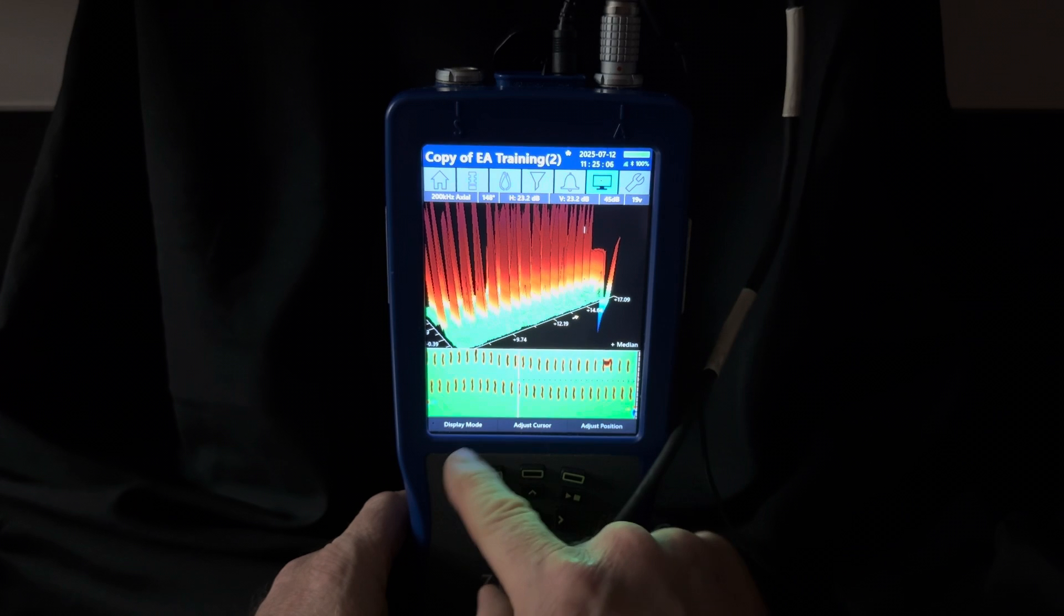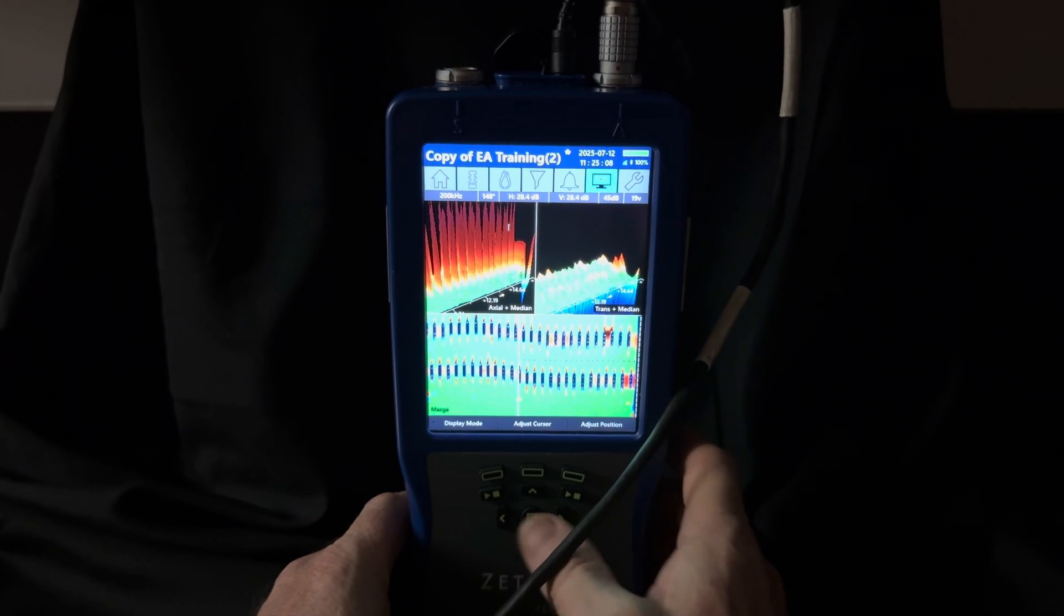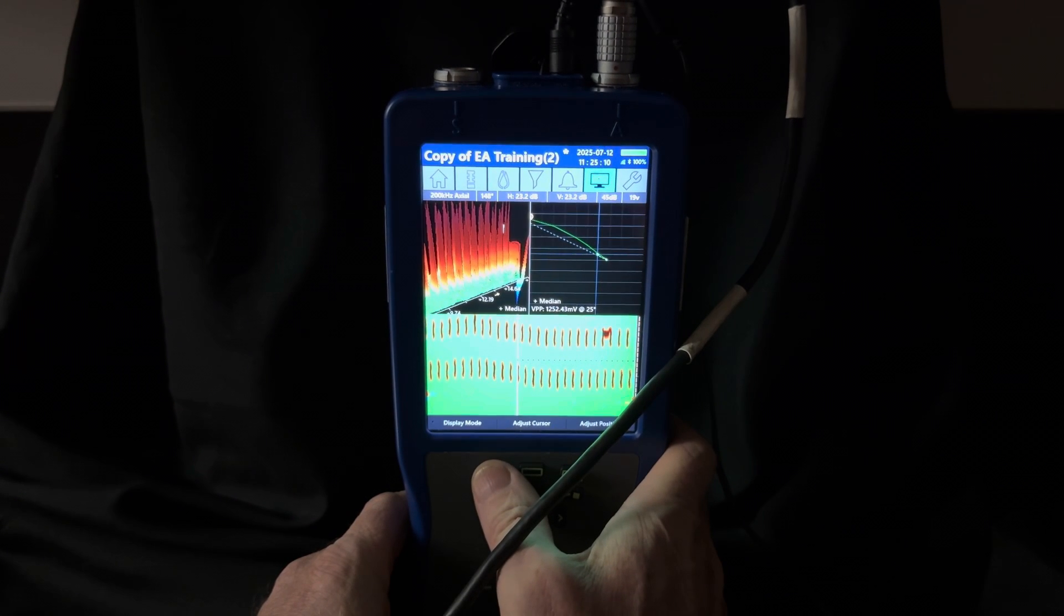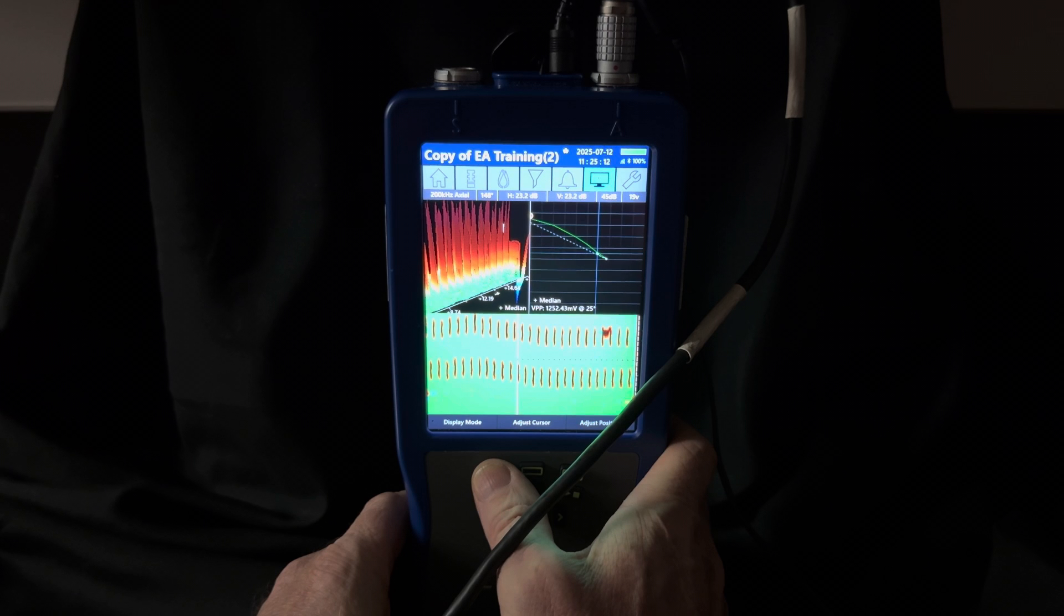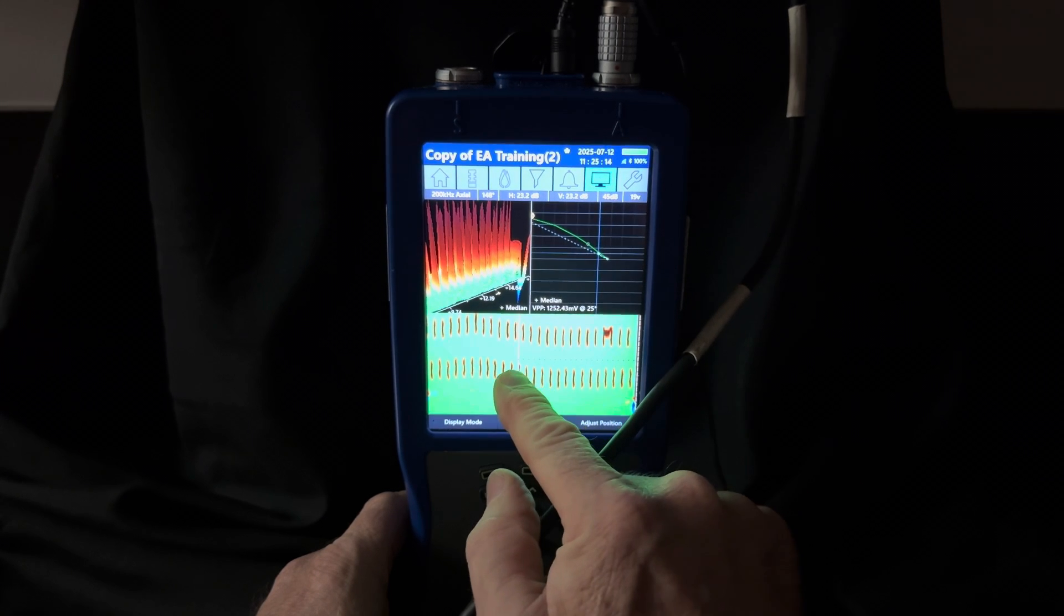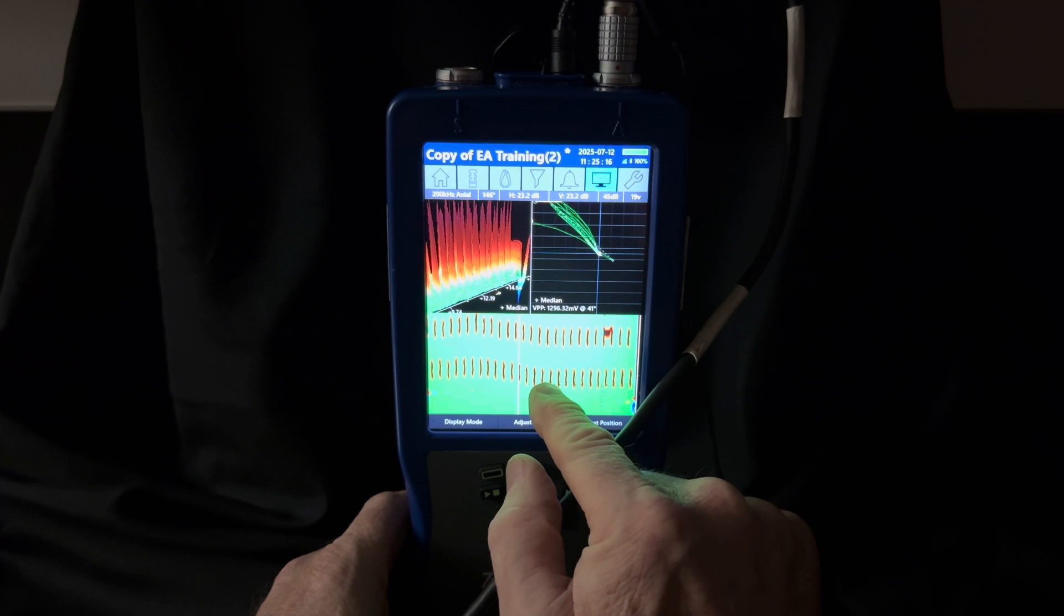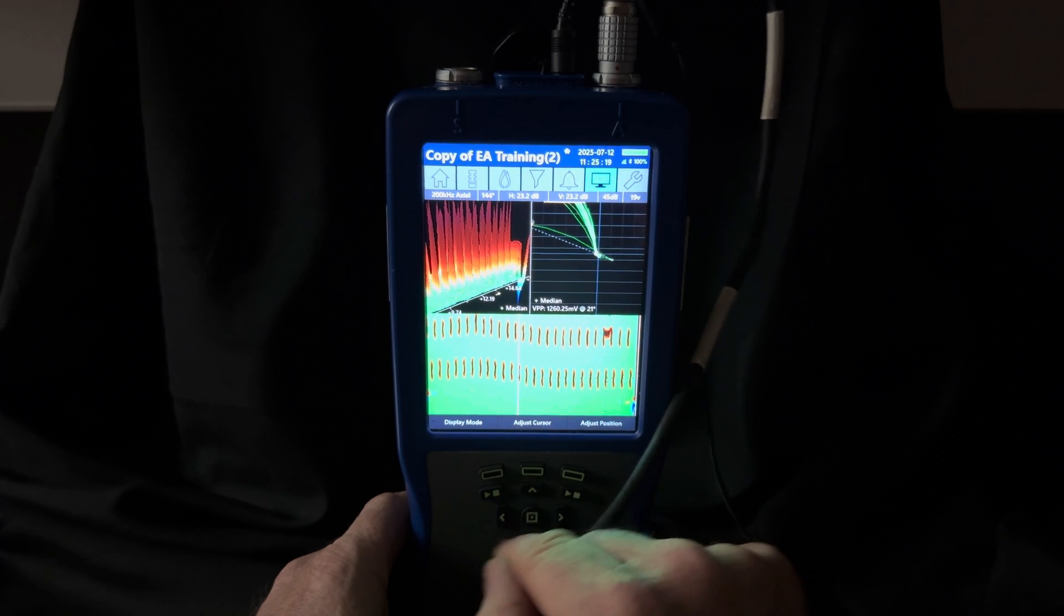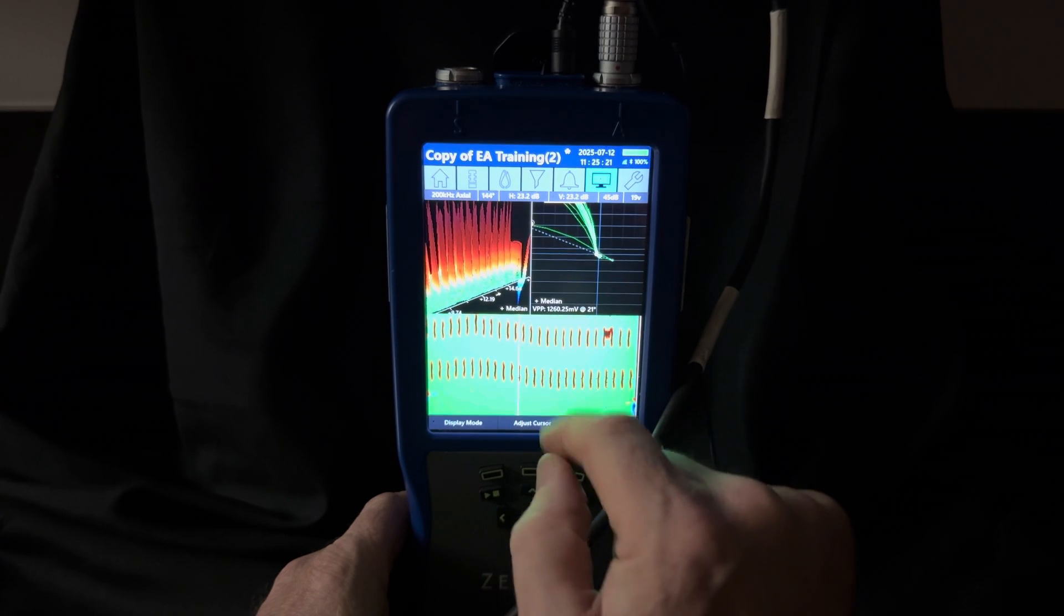Now there's multiple ways to look at the data. I'm going to go into the display mode here and just sort of toggle through some of the different displays we can choose. Here's the Lissajous view.